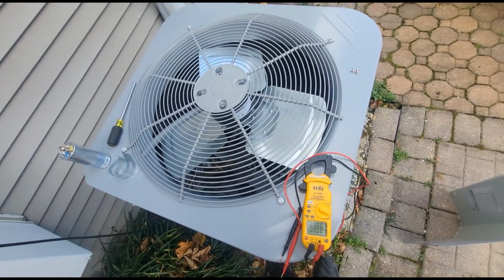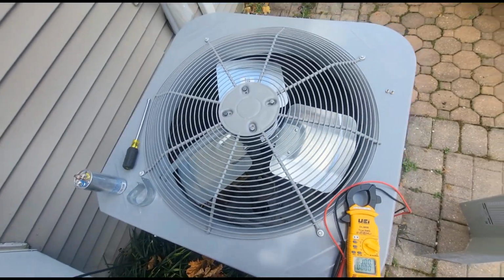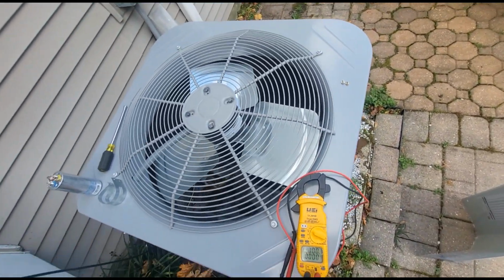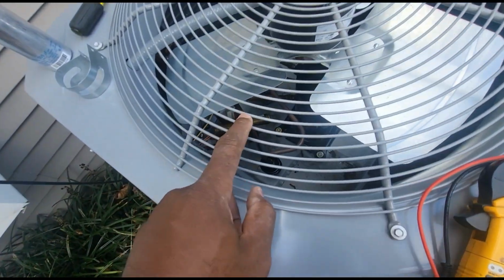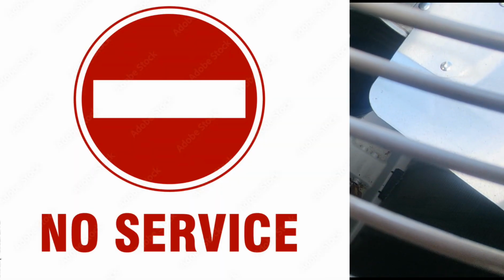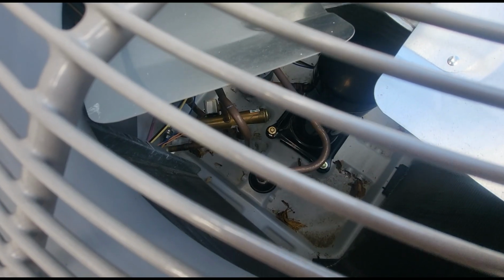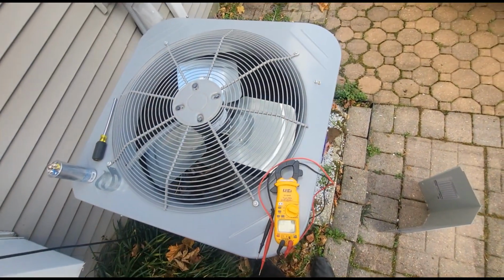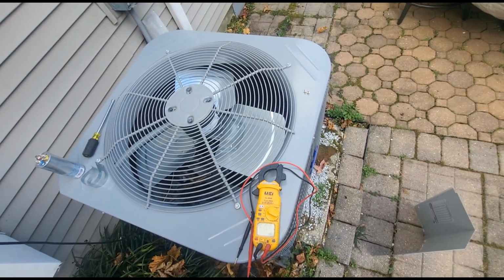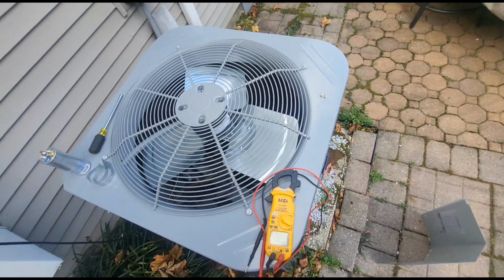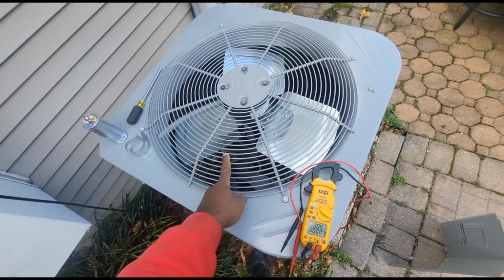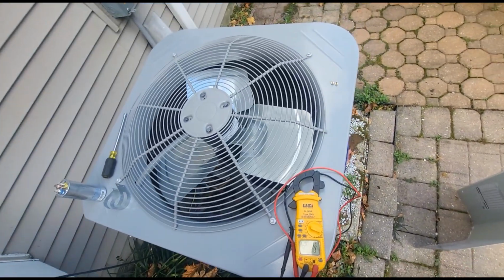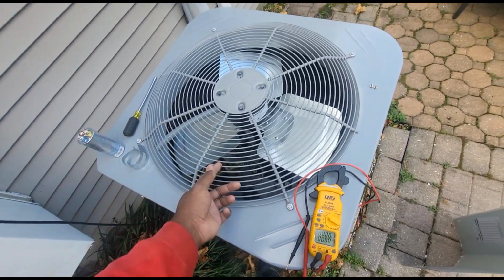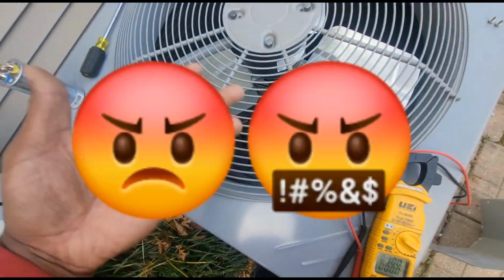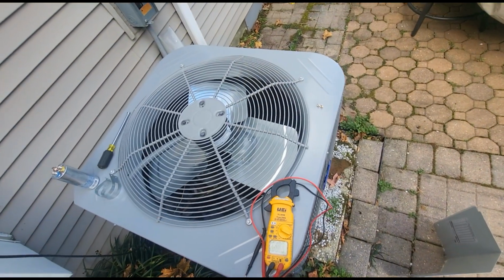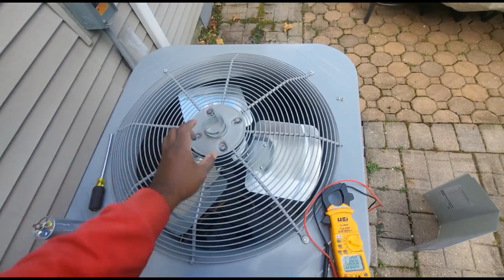Let me know in the comments if you guys had stuck reversing valves, what methods you tried. This reversing valve is hermetic, meaning it's non-serviceable, so if any internal mechanism sticks inside reversing valves, there's really not much you can do. If you get lucky and unstick it, kudos to you. But most of the time, I don't want to deal with the headaches of unsticking it and then getting a call back at 2 o'clock in the morning that the heat pump is blowing out 40-degree air in the winter. So let me know what you guys think in the comments.